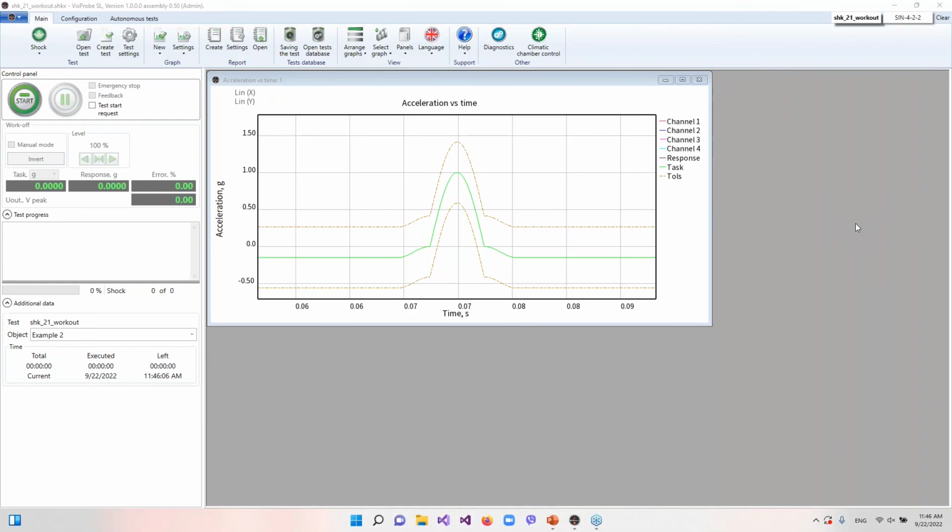There is a question about strain gauges, whether they operate in the same way in force control. Yes, they do, basically. But I should mention that force control is now only available in sine and fatigue tests. But in terms of these protections, the operation is the same.